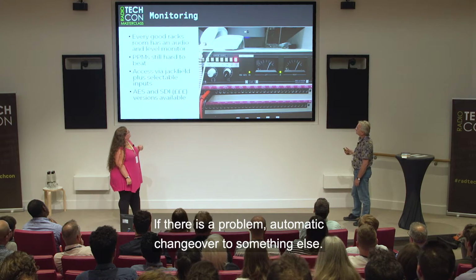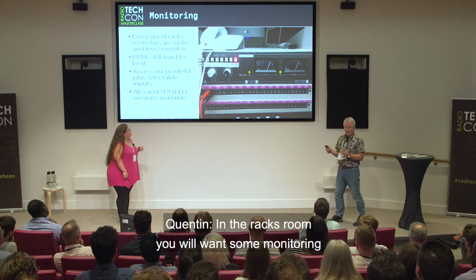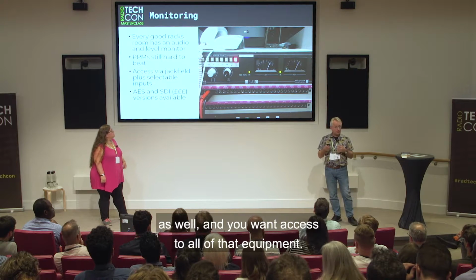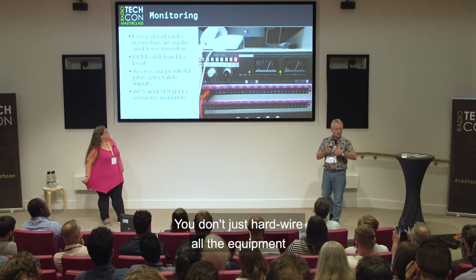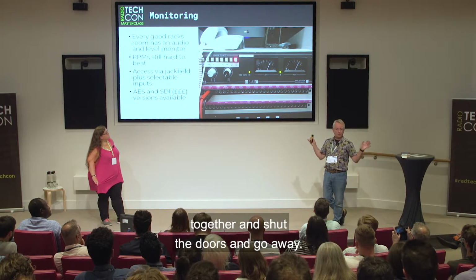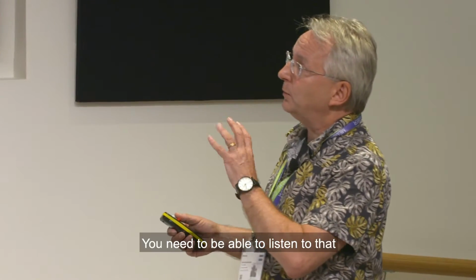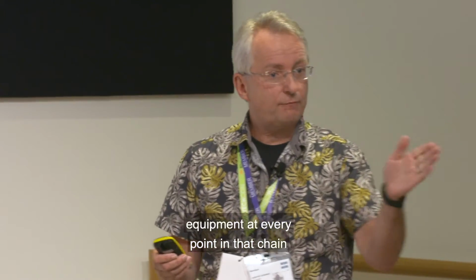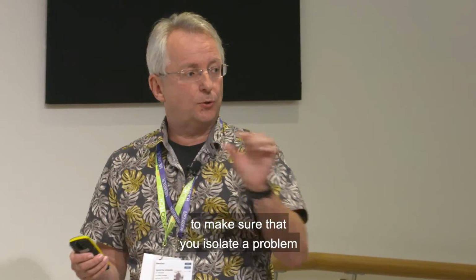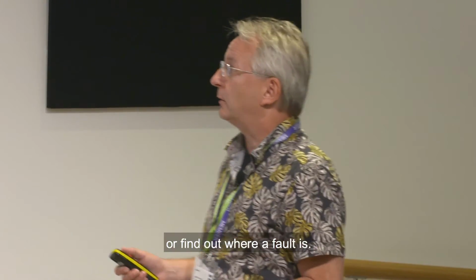In a racks room, you will want some monitoring as well, and access to all of that equipment. You don't just hardwire all the equipment together, shut the doors and go away - you need to be able to listen to that equipment at every point in the chain to isolate a problem or find out where a fault is.